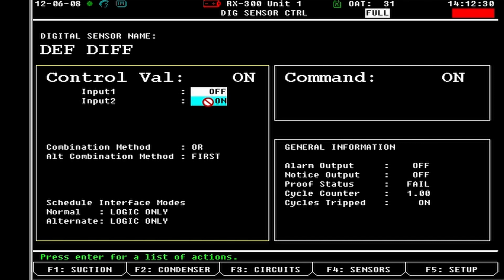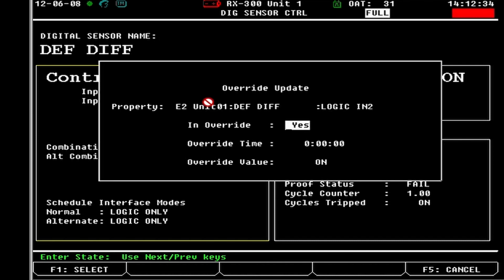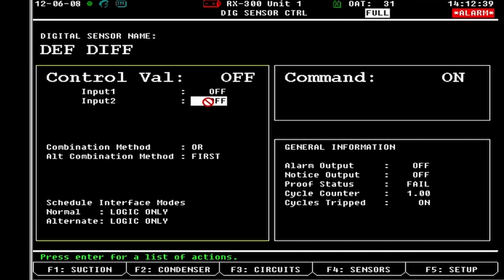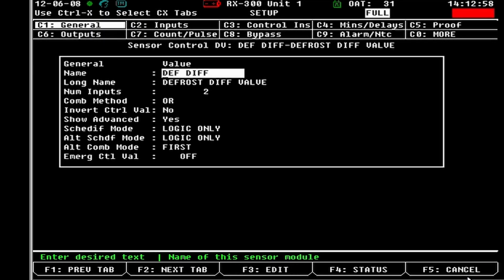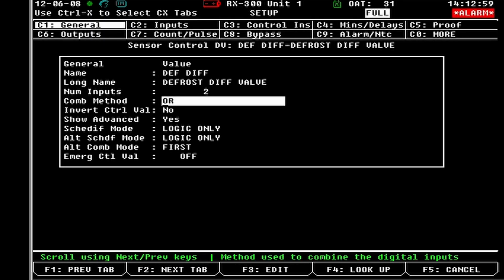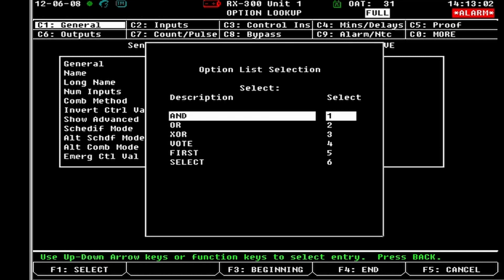If we go down here and we cycle this guy off, change this to no. So it's cycled off. See, it's an alarm because we have the command on off. So it just switched. So that same thing, if you change your update rate, it'll do that. If you were to change this to and, I'll show you how it reacts. So if we go down here and we hit F4 lookup and we change this to and.